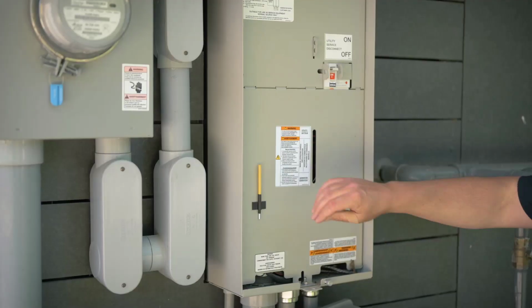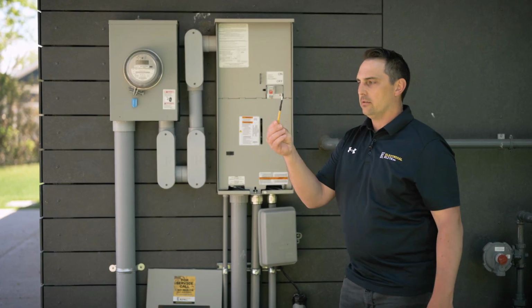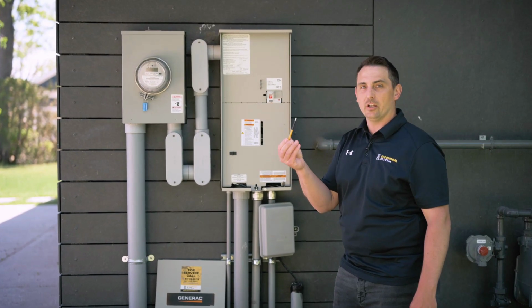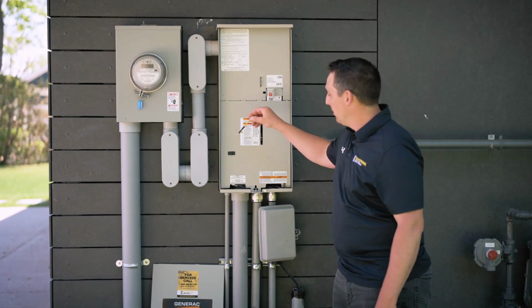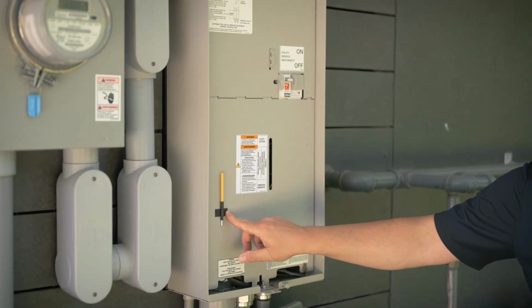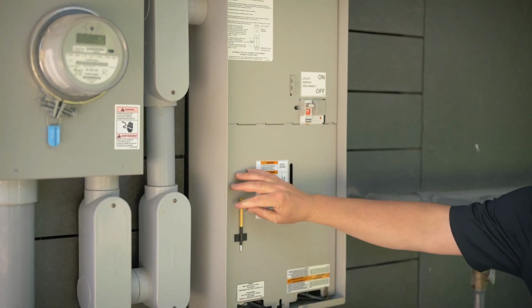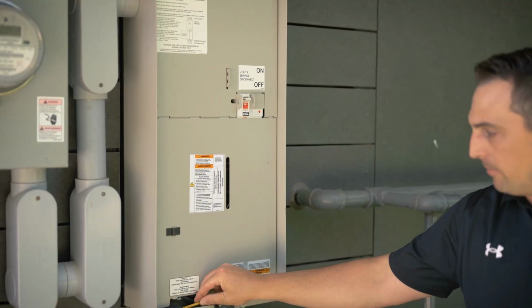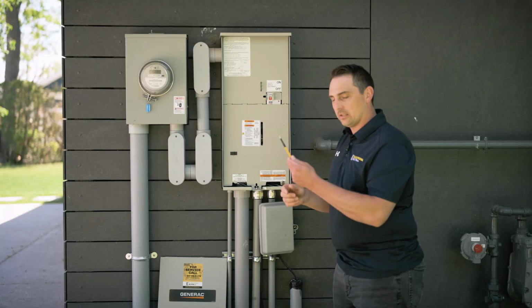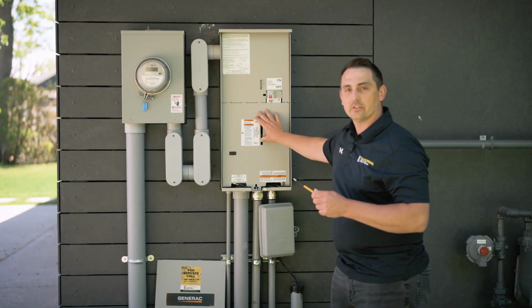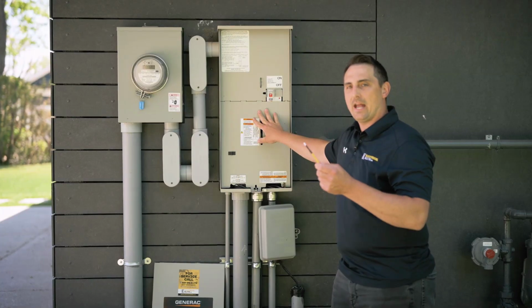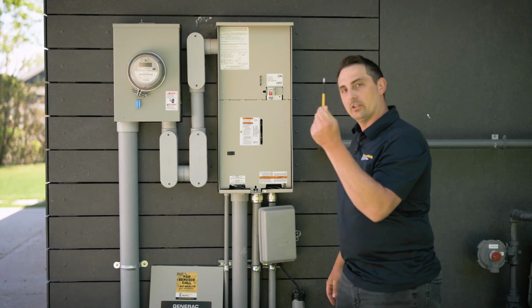In your ATS, you should see this little yellow handle tool. It's not going to be used very commonly, but in an emergency situation it is good to have, and make sure that you have it with the transfer switch. Sometimes this plastic clip doesn't stick to the cover real well, so this may actually end up in the bottom of the switch. What is this little tool? If the mechanism fails inside the ATS, you can manually transfer the transfer switch with this tool. Only competent and trained personnel are to operate electrical equipment, specifically using this little tool.